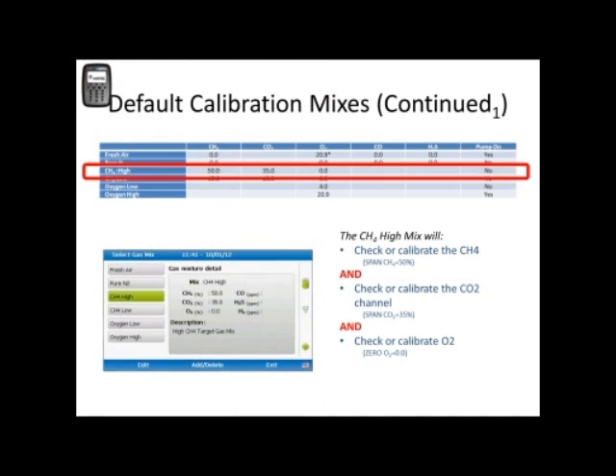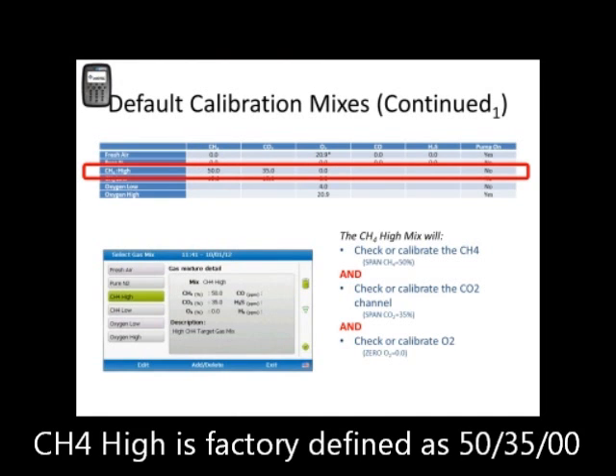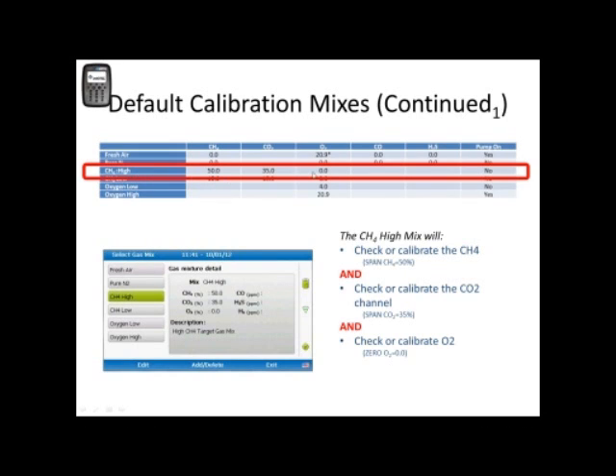Again, the default gas mixes are pre-configured from the factory. Focusing on the CH4 high gas mix and keeping in mind those 3 basic commands that we discussed at the beginning that the GEM5000 recognizes. Under this gas mix, we can clearly see that this mix will check or calibrate the CH4 to 50%, check or calibrate the CO2 to 35%, and check or calibrate the oxygen to 0, and do nothing for the other channels.